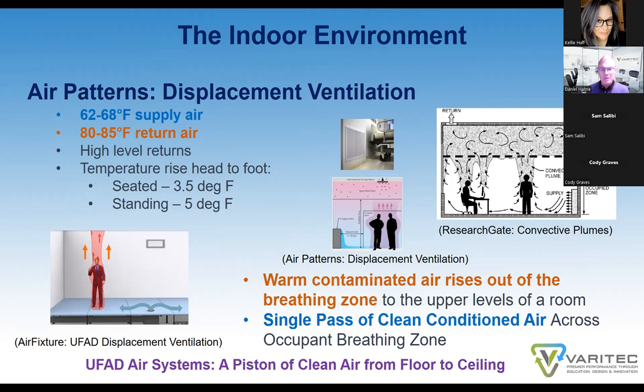Unlike mixed air systems that create uniform temperature within an environment by injecting air at high velocity through diffusers, this technology actually brings cooler air at very low velocities lower to the zone, creating a thermally stratified environment: roughly 70 degrees at the floor, 75 degrees at a thermostat, 80 to 85 degrees in the upper levels of the room, depending on the ceiling height and the amount of load in that room.